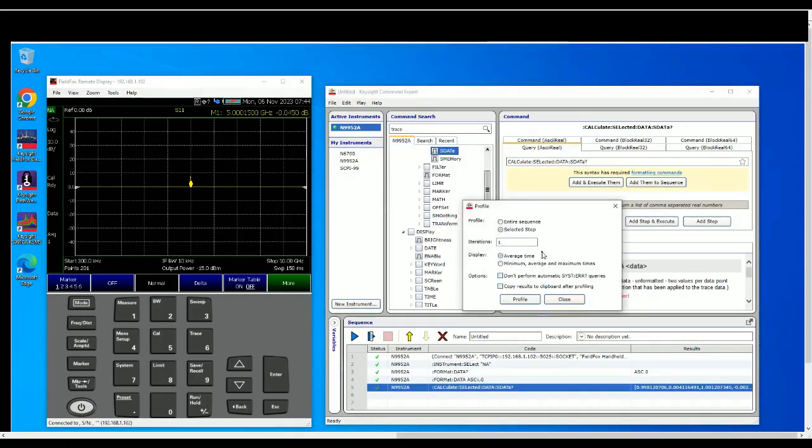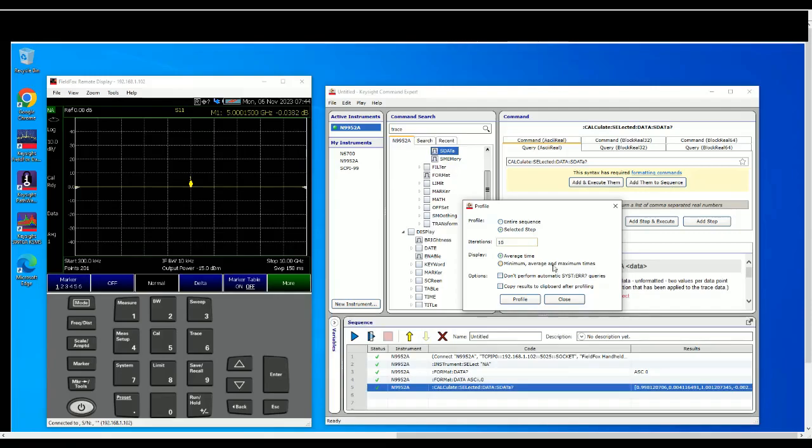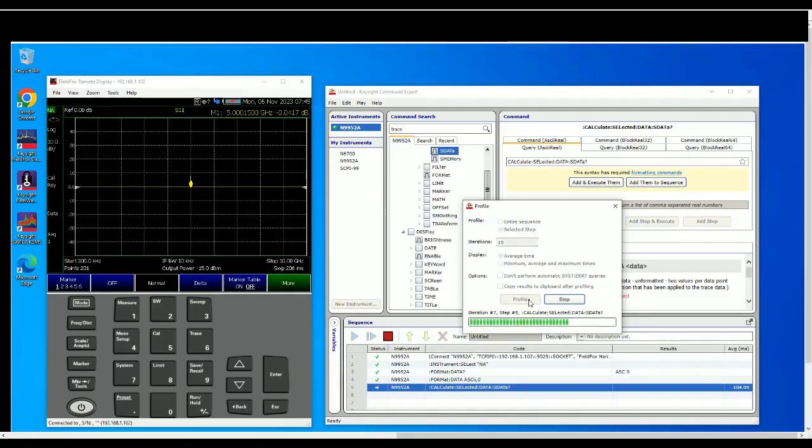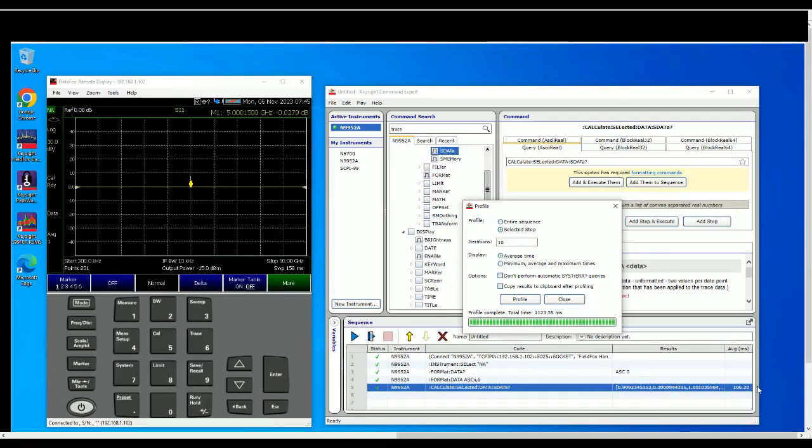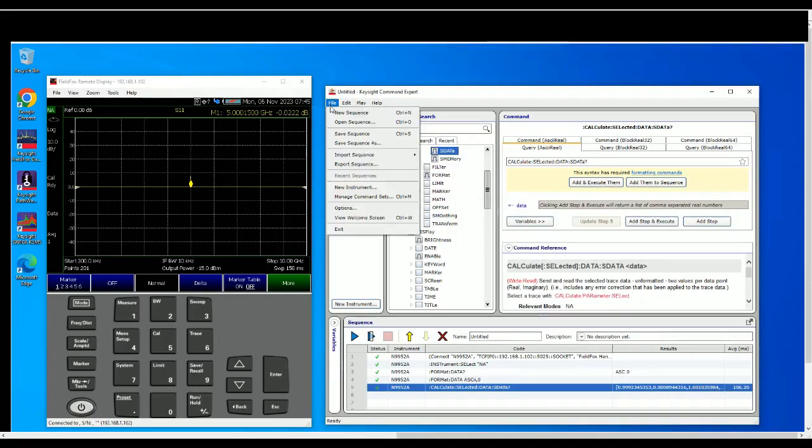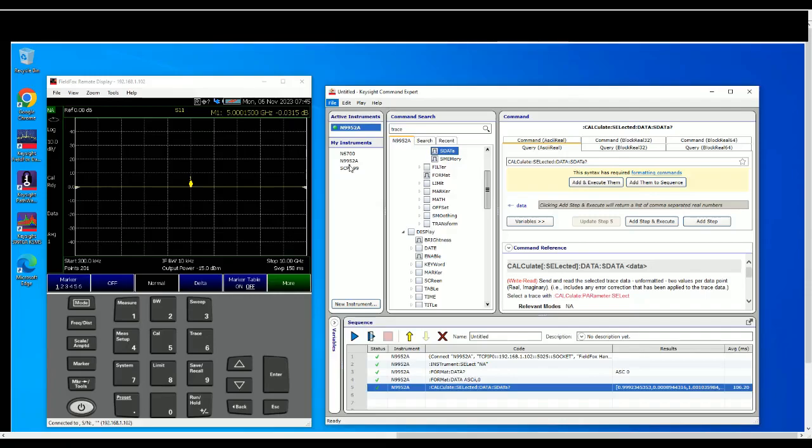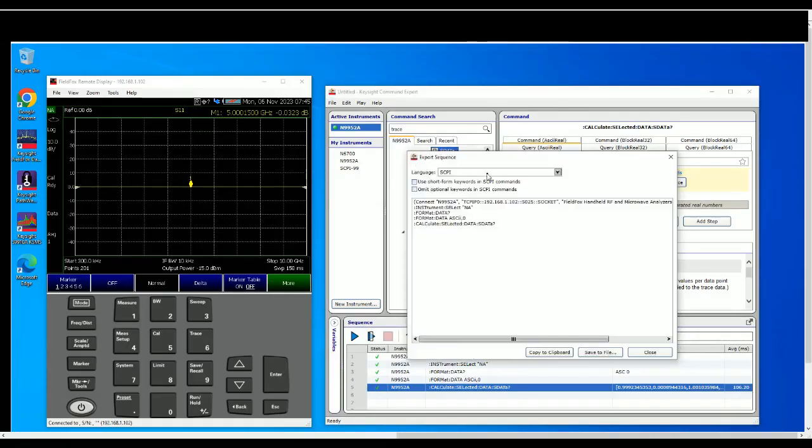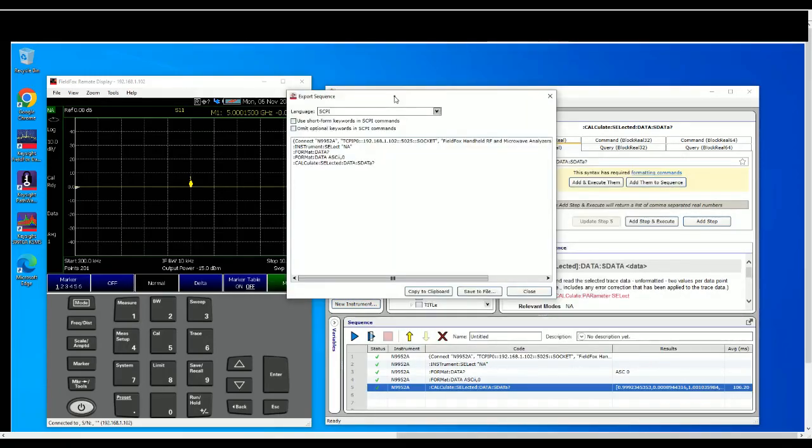So this is the iteration side on the profile and then you can get let's say 10, start 10 iterations. So it's one, two, three, four, five, six, seven, eight, nine, ten. So every trace average is 121.6 milliseconds. So you can either do that or you can actually export the sequence to a certain programming language. So by default is SCPI, this is not the SCPI that we use now over here.